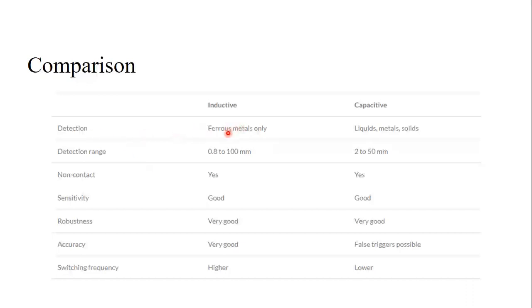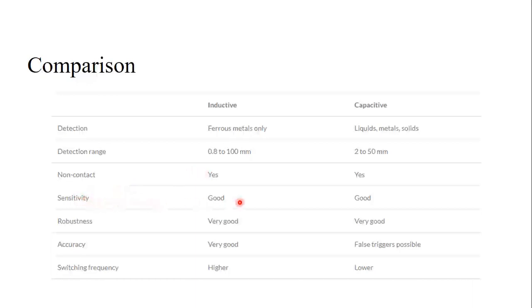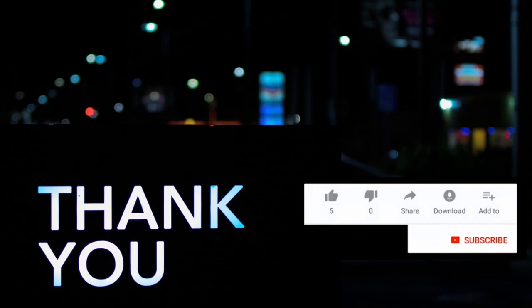Here is a comparison between both sensors. For detection: inductive sensors only detect metals, while capacitive sensors detect liquids, metals, and solids. Detection range: inductive is 0.8 to 100 mm, capacitive is 2 to 50 mm. Both are contactless. Sensitivity and robustness are good for both. Accuracy is very good for inductive sensors, with some false triggering possible in capacitive sensors. Switching frequency is higher for inductive and lower for capacitive.